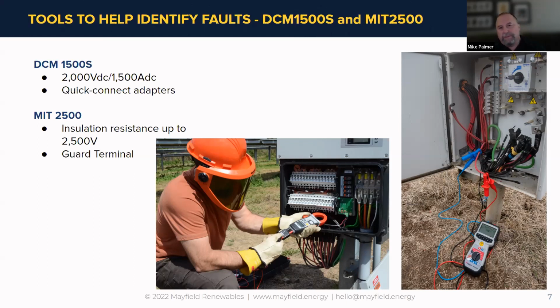Just understand that only our big box units had those, 5, 10, and 15 kV, forever. Now we have the ability to have the guard terminal in a handheld device. When you're carrying all you're carrying now, you could fill the back of a golf cart, so it's nice to have a handheld with the guard terminal on it. Once again, you're not going to use it every day. Some of you may have bought this unit and never used it yet, but it's there if you need it. It'd be great to get some feedback in the Q&A if anybody has had to use a guard terminal.